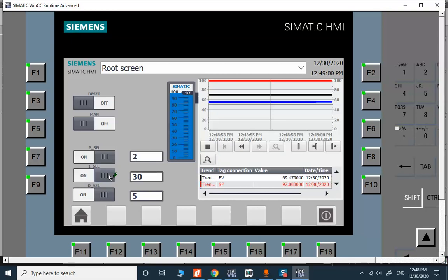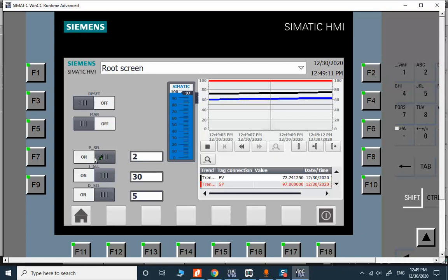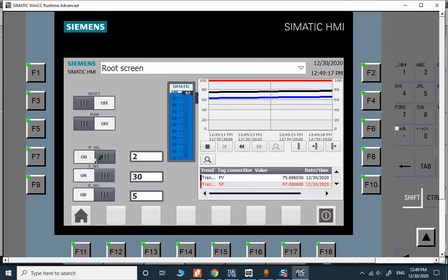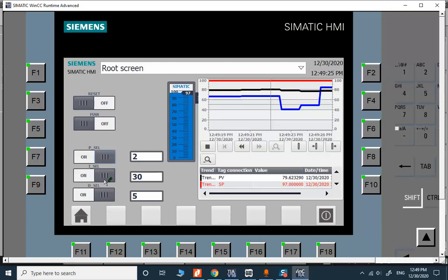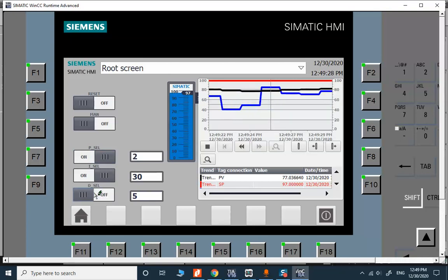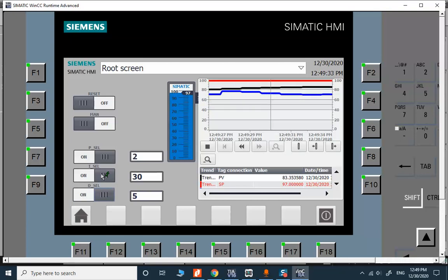When you are in steady state or in startup you can change any selection you want. If you want PID, you can do that in manual mode. Be careful of changing these variables when the controller is in automatic mode or it's in operation. It's very dangerous for the process, so be careful.